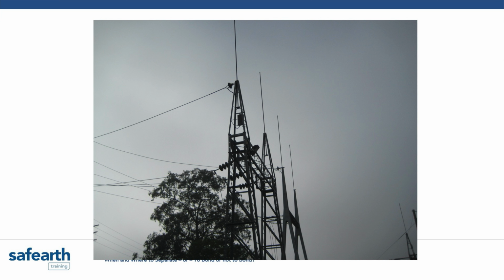That substation's at Kellyville in Sydney. We injection tested over that feeder and the substation was fine, no real problems there. It had lots of connections into lots of things and a really low earth potential rise. But the last structure out across the road had a voltage rise of thousands and thousands of volts, all due to induction into the overhead earth wire because it wasn't earthed at the very end of it.